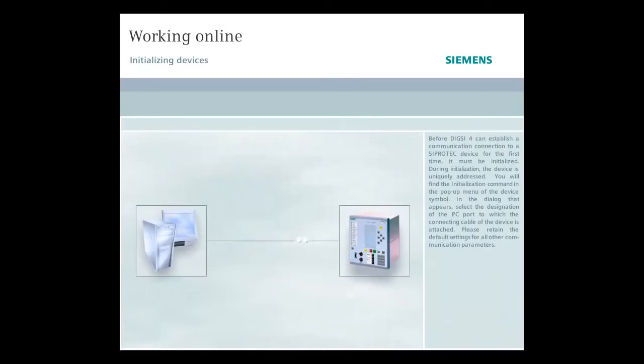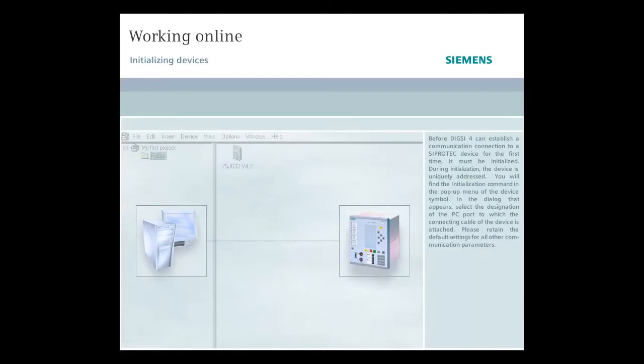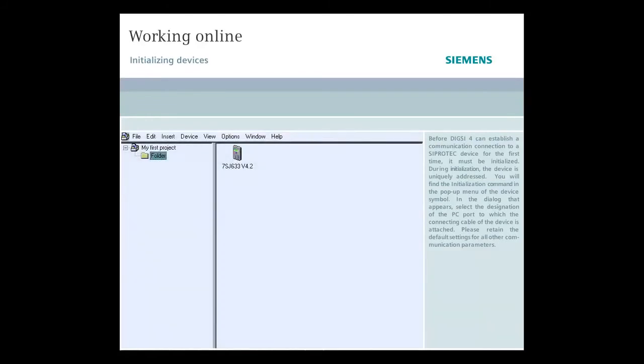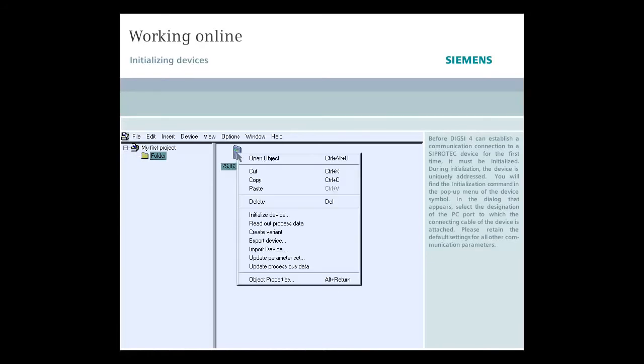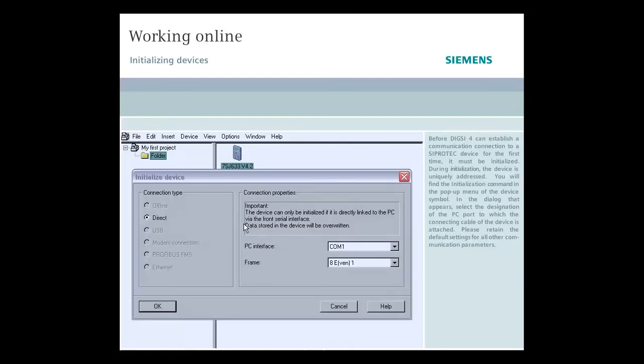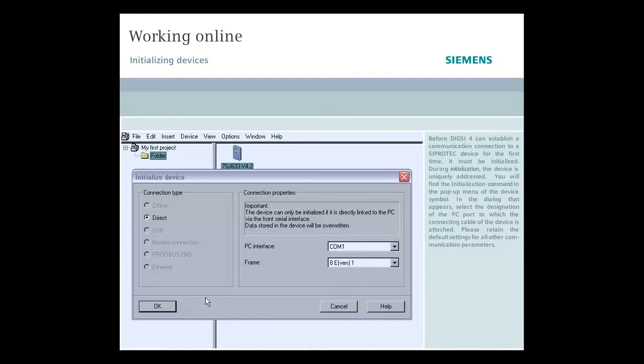Before DIGSI 4 can establish a communication connection to a SIPROTEC device for the first time, it must be initialized. During initialization, the device is uniquely addressed. You will find the initialization command in the pop-up menu of the device symbol. In the dialog that appears, select the designation of the PC port to which the connecting cable of the device is attached. Please retain the default settings for all other communication parameters.